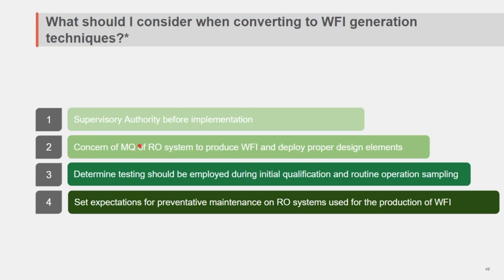And secondly, there are concerns about the microbiological quality of the RO system used to produce WFI. We have to deploy a proper design element as well as a good sanitization strategy to control the biofilm growth as well as to maintain a good microbiological quality within the system. And number 3, we have to determine the tests that should be deployed during initial qualification as well as for future routine operation sampling. And number 4, we set the expectation for the preventive maintenance on RO system used for production of WFI. And all these could be achieved with our Aquavista portal as well as our service maintenance contract review.